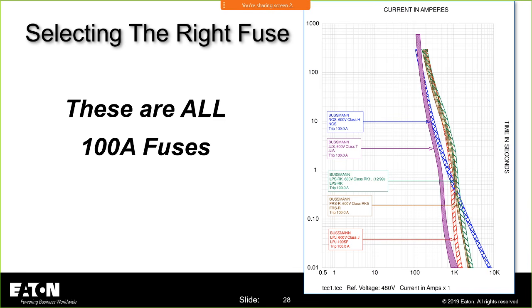But in any case, there's your Class H, this is your Class T, and these other three look pretty close. Those are your RK5s and your RK1s. Your RK5 is the brown one. That's this guy right in here. The green one is your RK1. They're very similar, but you'll notice that the RK1 is a little bit further over to the right than the RK5. And maybe in this hump, there's a little bit of a difference. And then you have this Class J. You still get a little bit of this hump in here, but you get a little bit closer to whatever your load currents are.